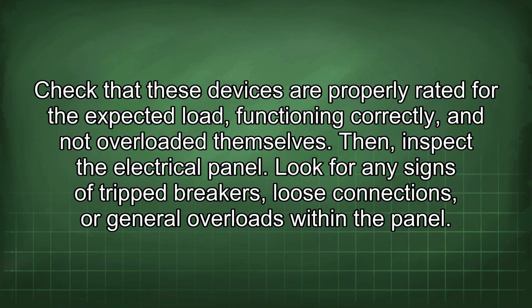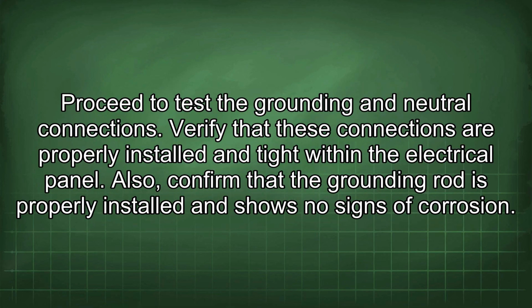Then inspect the electrical panel. Look for any signs of trip breakers, loose connections, or general overloads within the panel. Proceed to test the grounding and neutral connections. Verify that these connections are properly installed and tight within the electrical panel. Also, confirm that the grounding rod is properly installed and shows no signs of corrosion.